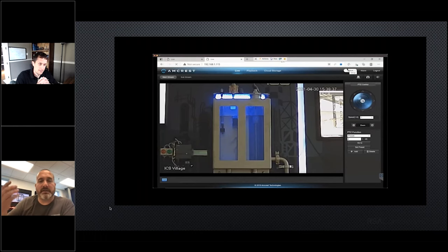We got somebody who changed the level set point. We got some alarms in. The tank did not overflow — the process flow did not go on the ground — because the tank shut off once it hit the high level switch. Important part to remember as we go through the presentation. Then the tank drains out because it hit the high level switch.